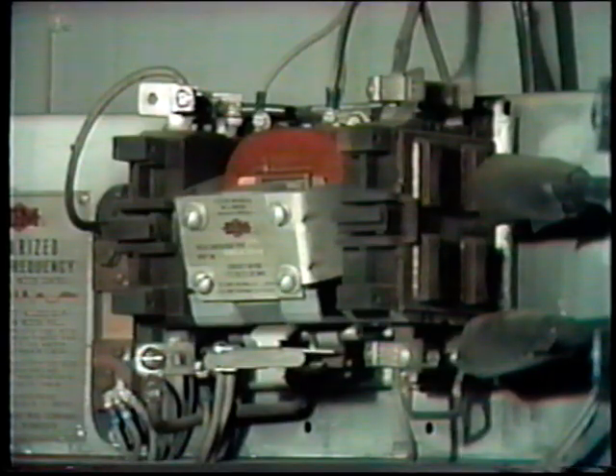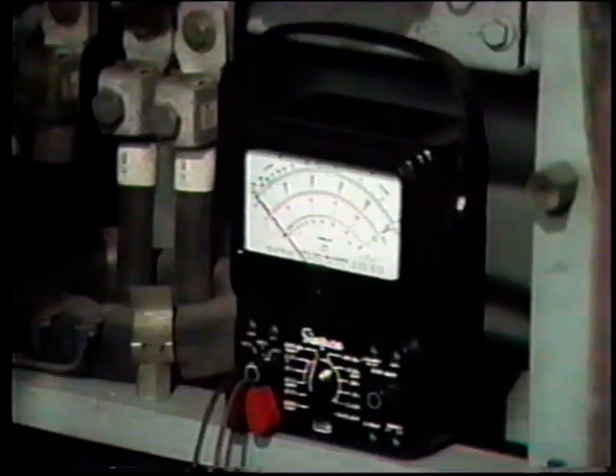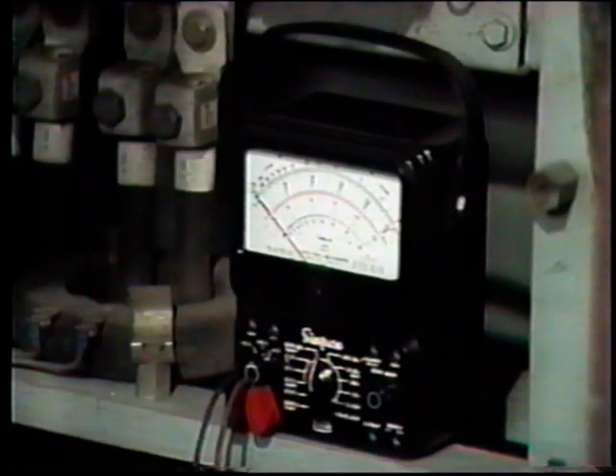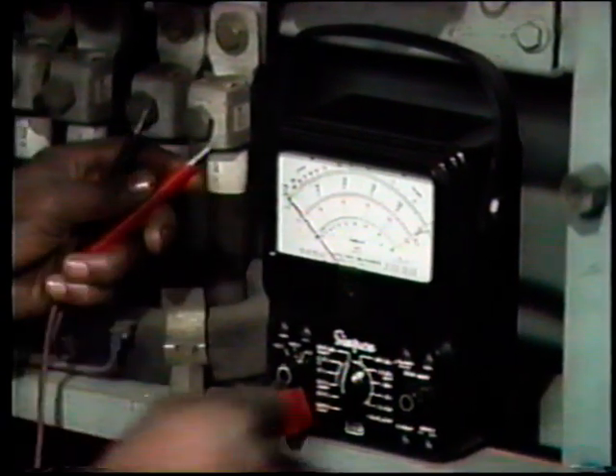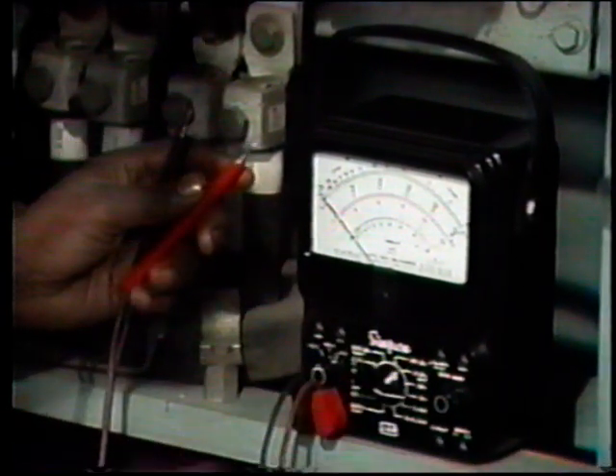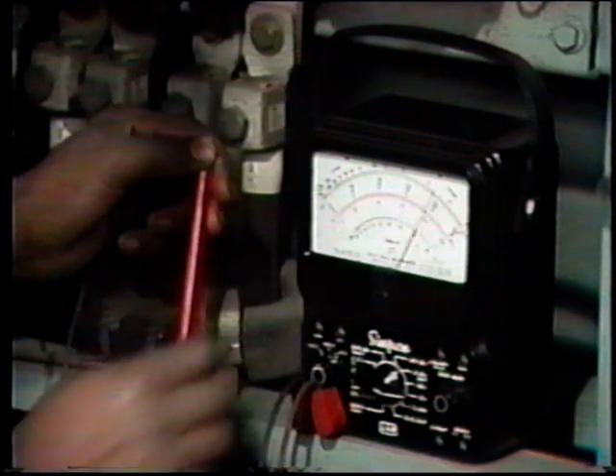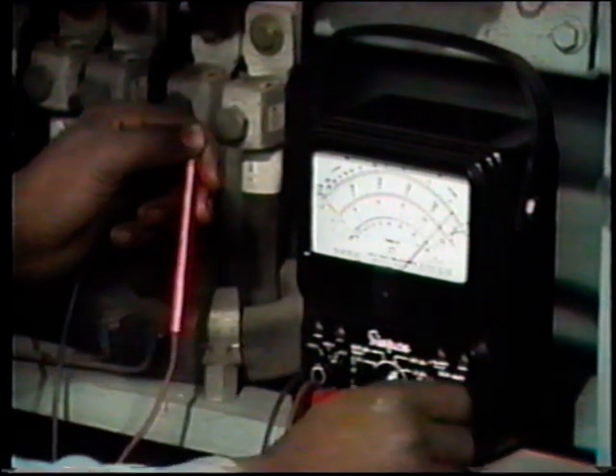We'll test the field relay coil of this controller. When we test the field relay coil for opens, we will also be testing it for shorts. After the controller has been completely de-energized and tested to make sure that it is de-energized, the multimeter is set to its resistance scale and zeroed.